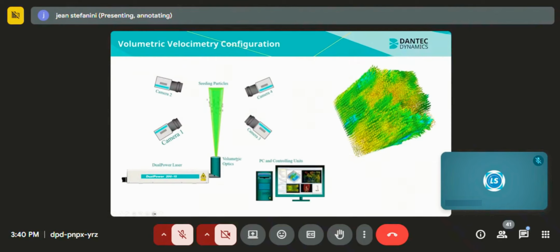So in terms of acquisition rate, depending on the type of system you are looking for, we can capture data starting at 15 Hertz. So you get 15 velocity fields per second. But it can go up to kilohertz or tens of kilohertz. The only difference will be really the laser you are going to use and the camera you are going to use, because for a high repetition rate, you need a high-speed laser and you need a high-speed camera as well.